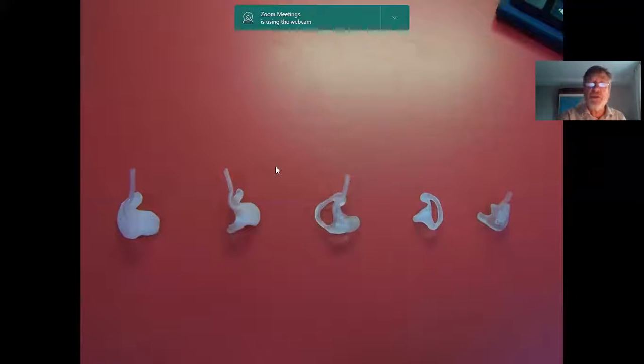All right, so mainly the two types of ear molds: full shell, silicone, lucite, skeleton. And the tubing is called number 13. Don't ask me why, it's called number 13 tubing. And number 13 tubing is, and I'm going to stop sharing so you can see this again. Number 13 tubing is, if I pull it off, 2 millimeters in diameter. You see that? 2 millimeters in diameter. That's the width, or that's how open it is.